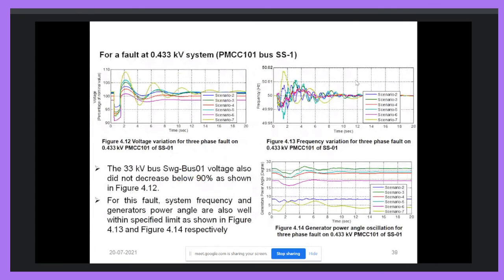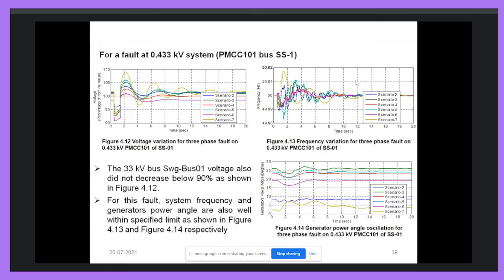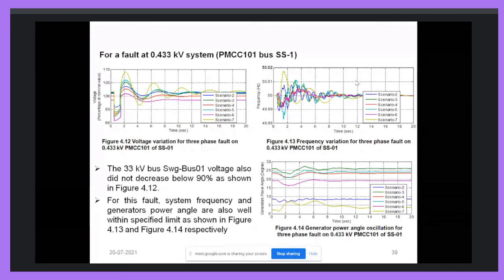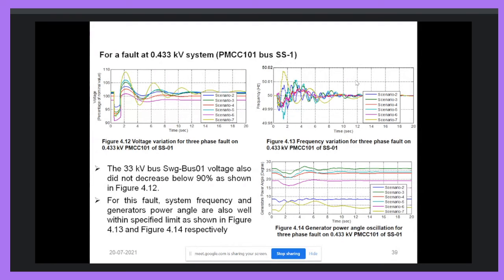Here we can see in case of the fault occurred on a 415 volt system, the voltage is not much varied. It is about 92% of the rated voltage, and frequency is also within the value. So when the fault occurred at the 415 volt distribution voltage level, its effect will be minimum. So we have to prepare the database so our ANN will be capable of identifying the severity of the fault. We have to train the network so that it can understand the severity of the fault. But other conventional load shedding techniques will not understand the severity of the fault, because the severity of the fault also affects the operation of the system.